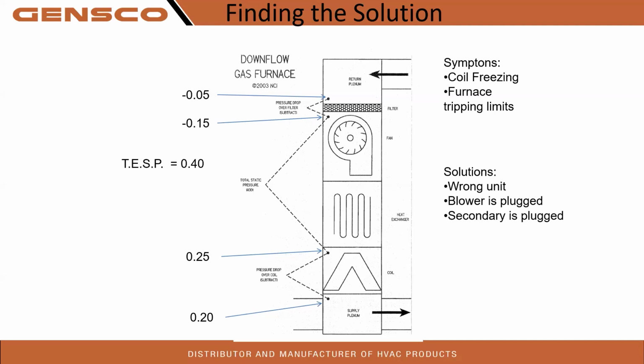Secondary could be plugged on a 90+ furnace. We have a primary heat exchanger that's pretty wide open, but that secondary is kind of tight. Man, I have found a raccoon in one, so that was plugging up the secondary. That's kind of gross. Bad or wrong motor. This does happen once in a while. We get a wrong motor put in there.